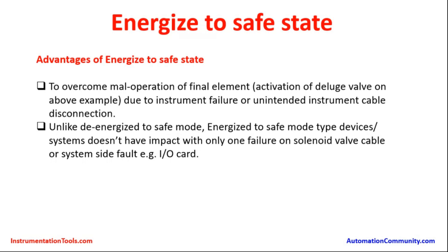In the de-energized state, power is going to the solenoid valve, so whenever there is a cable cut or I/O card failure, it leads to the closing of the main valve — which is not the case in Energize to Safe State. As long as power is not flowing through the loop, failure of the module does not have impact. However, there shall be system side fault indications that require the operator and maintenance engineer's attention to attend to the fault and refix the issue or replace the failed module. These are the advantages of Energize to Safe State.